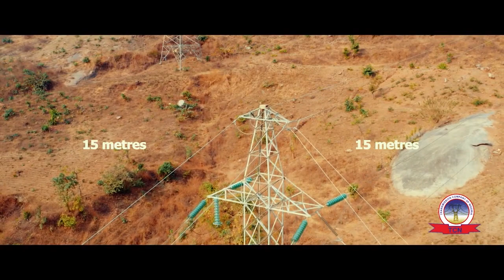Safety compliance simply means before erecting any structure around any electricity tower or line, there are safety distances you must adhere to. These safety distances are 25 meters on both sides of the electric tower in the case of a 330 kV, 15 meters on both sides in the case of a 132 kV, and 7.5 meters on both sides in the case of a 33/11 kV. These stipulated safety distance instructions are what we call right of way. If these simple, basic safety distances are adhered to, trust me, there will be less loss of property and lives resulting from cut transmission lines.